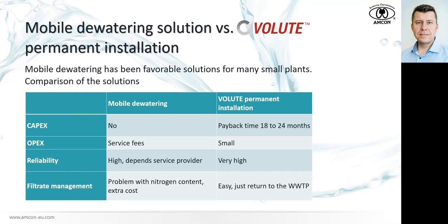For a purely decentralized solution, yes, you need to invest in technology — the Capex. But the Opex is very small due to low electricity consumption, low water consumption, and normal flocculant consumption. Reliability is very high: volute dewatering presses are low-speed machines, so any trouble approaches slowly — there's always time to fix and maintain. It's almost maintenance-free, requiring only a few minutes a day for cleaning and checkup, and it's very easy to plan future maintenance. Compare that with a centrifuge — a high-speed machine where problems happen quickly.